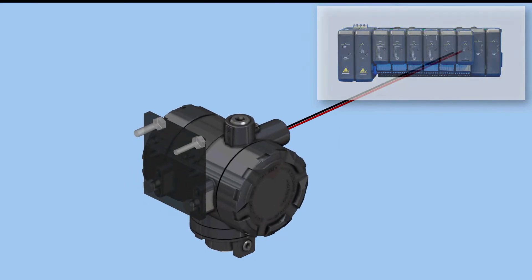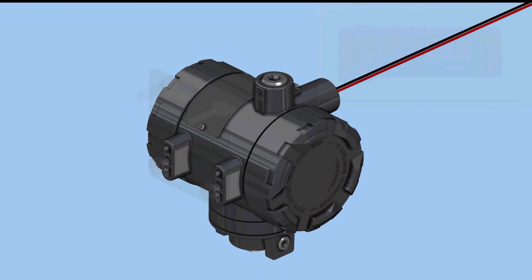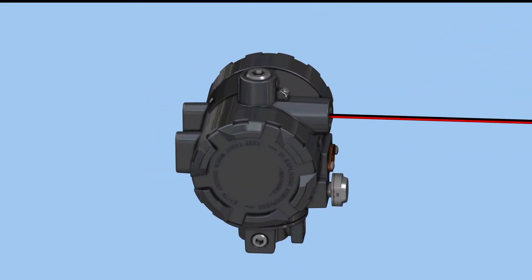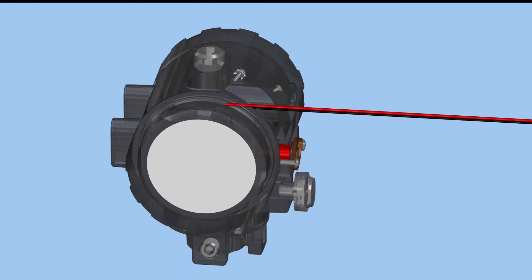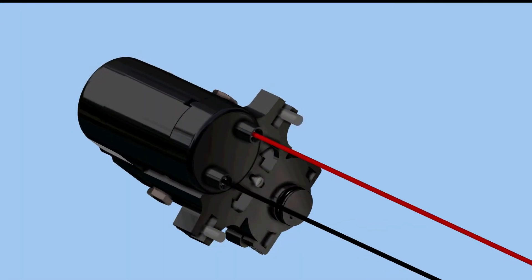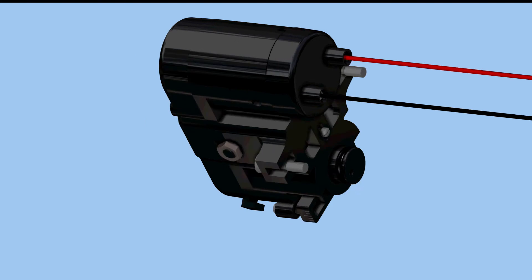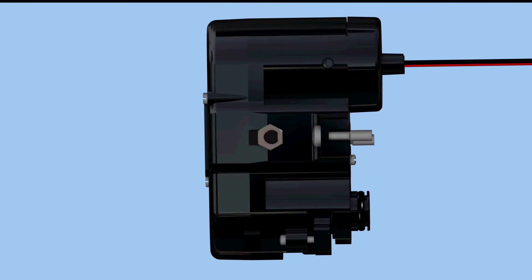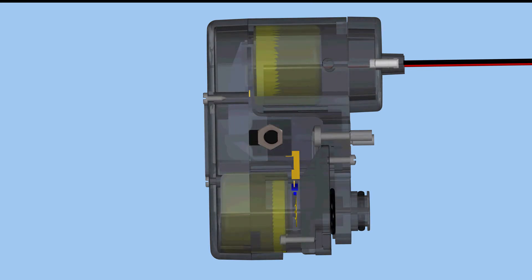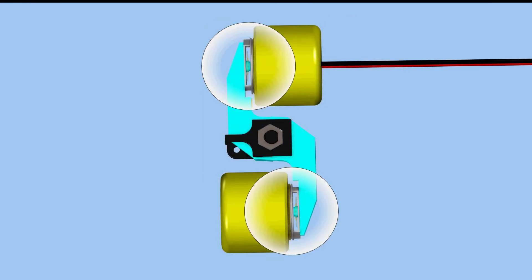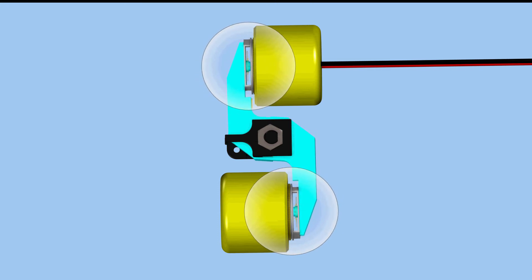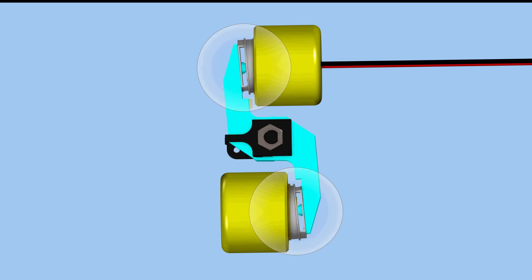In this animation, we have a 4 to 20 milliamp input signal that needs to be converted to a pneumatic output signal. A common pneumatic output signal is 3 to 15 PSIG. The electronic 4 to 20 milliamp input signal is applied to an electromagnet. As current is changed to the electromagnet, magnetism increases or decreases.